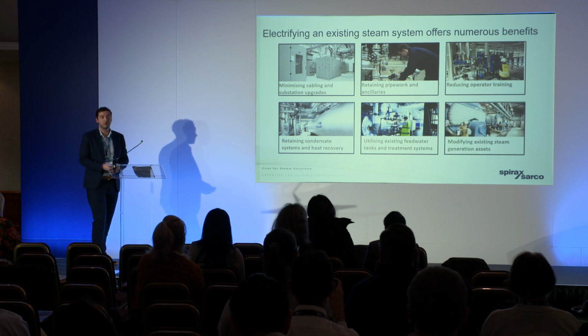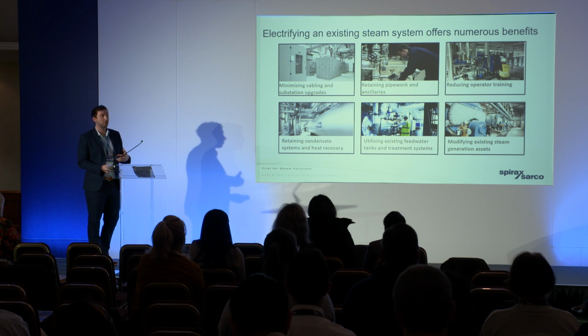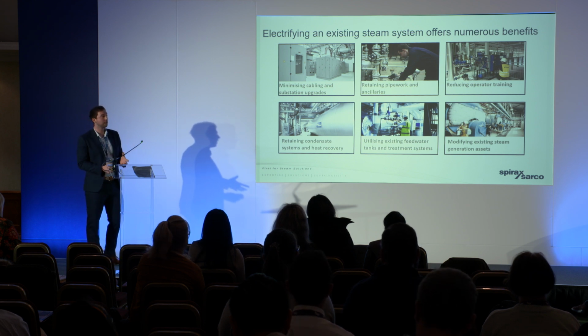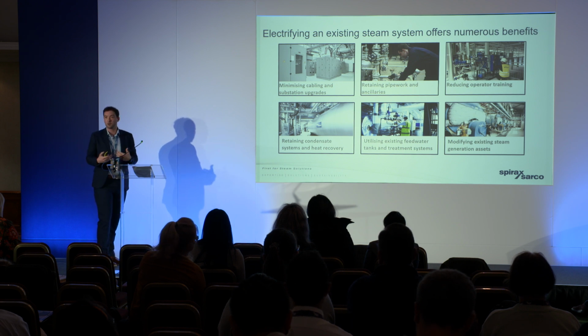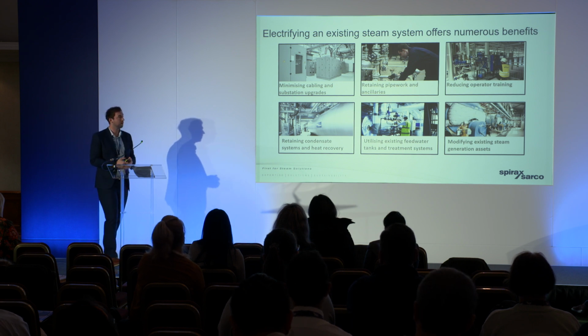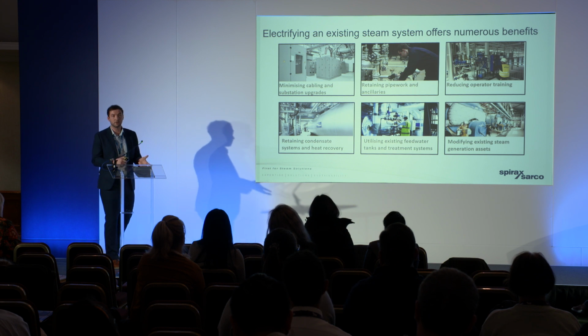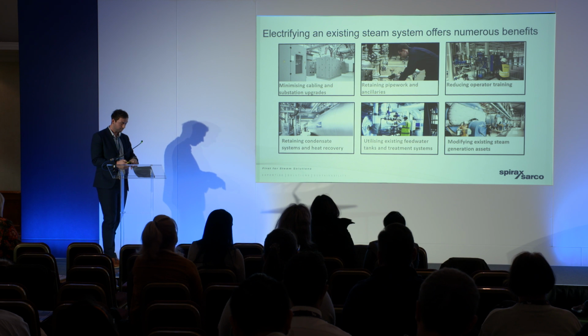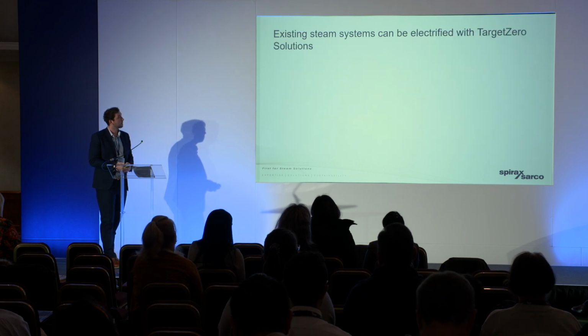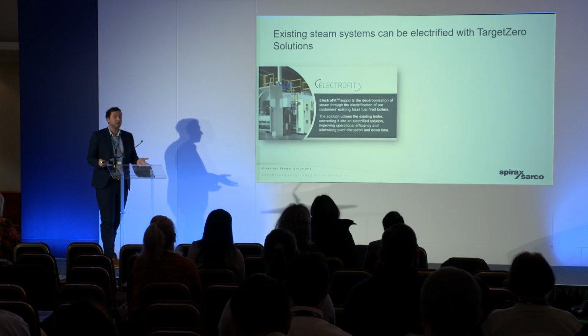And in some cases, when it's appropriate, we can actually utilize the existing gas boiler. We can change it from gas to electric. And really, that's our gold standard and what we want to be approaching. Go to a system, literally change the burner for electricity, and the system will continue to operate as it did before. And we've got some solutions that do that.